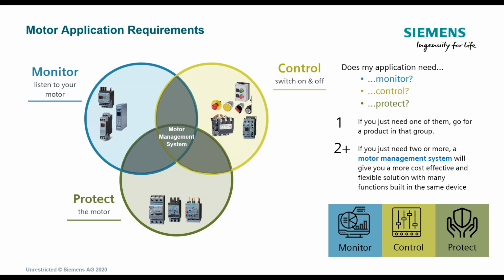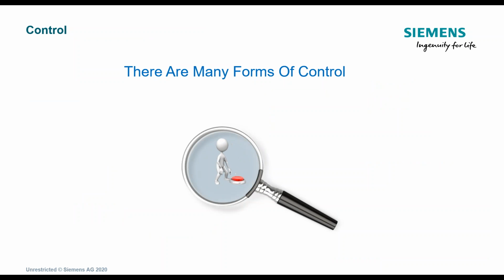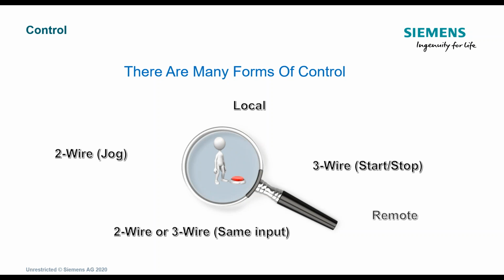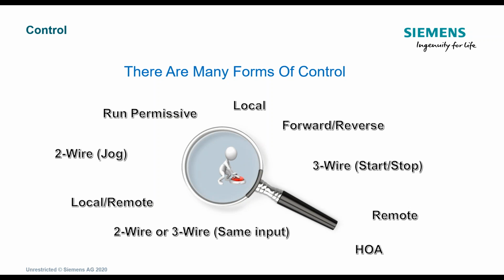With that in mind, this is where Siemens's motor management system comes into play, is that we cover all three of these aspects: monitor, control, and protect. So first off, let's talk about control. There are many forms of control with a motor. There's a 2-wire, 3-wire, local, remote, forward, reverse, run with permissives, interlocks, hand-off-auto, and then remote, and so forth.